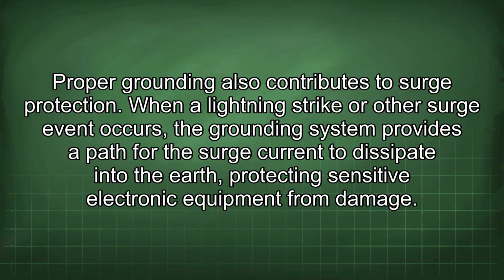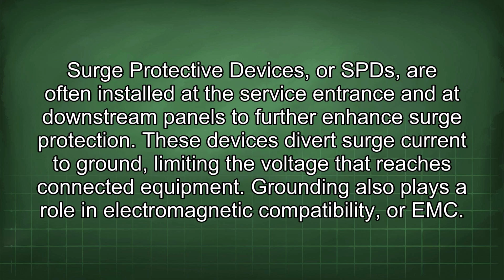Proper grounding also contributes to surge protection. When a lightning strike or other surge event occurs, the grounding system provides a path for the surge current to dissipate into the earth, protecting sensitive electronic equipment from damage. Surge protective devices, or SPDs, are often installed at the service entrance and at downstream panels to further enhance surge protection. These devices divert surge current to ground, limiting the voltage that reaches connected equipment.